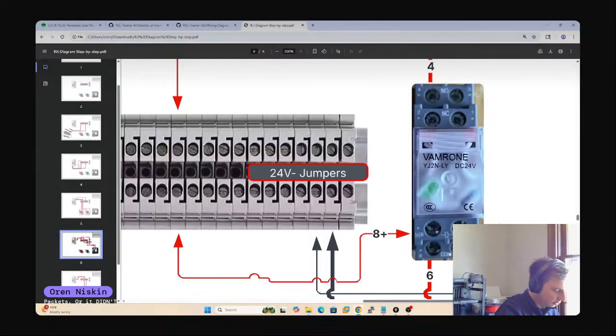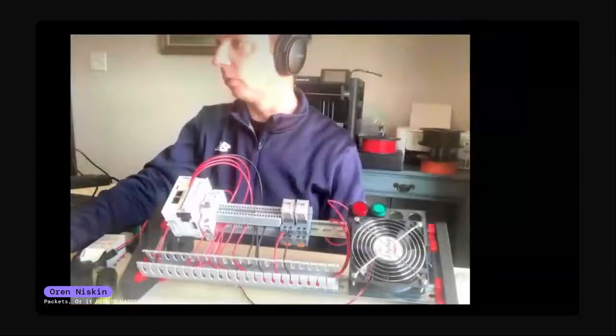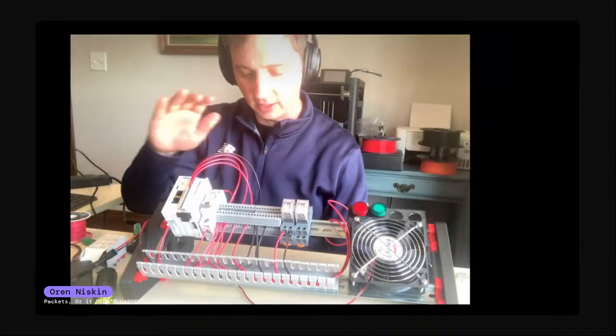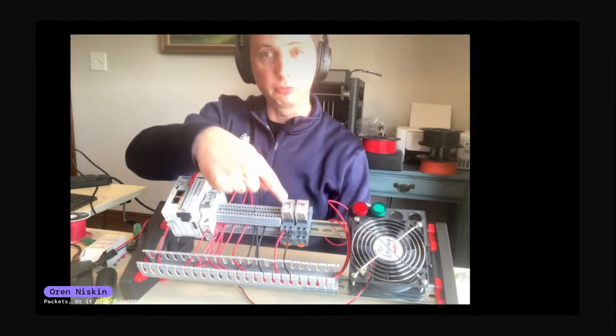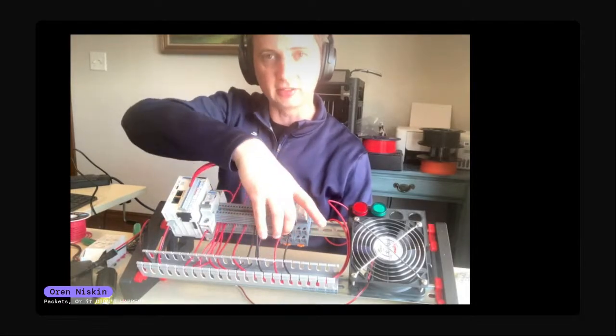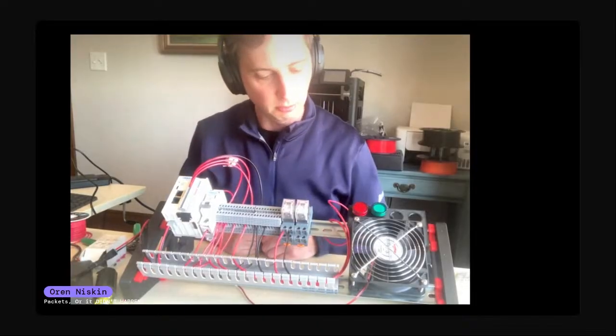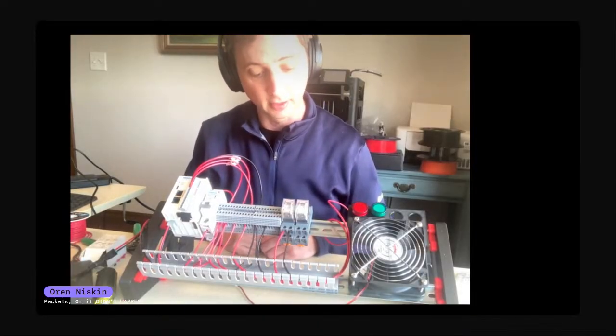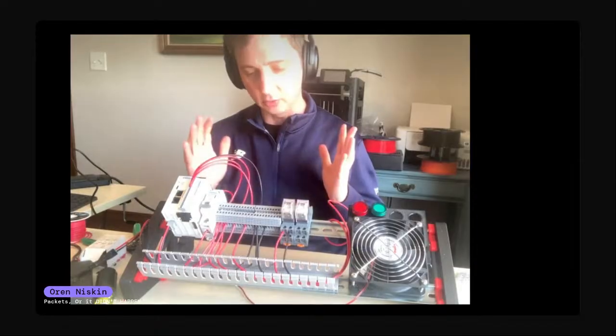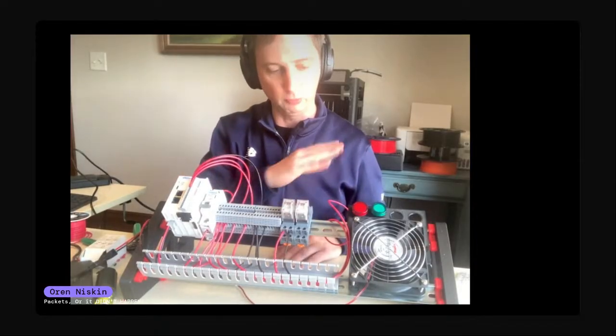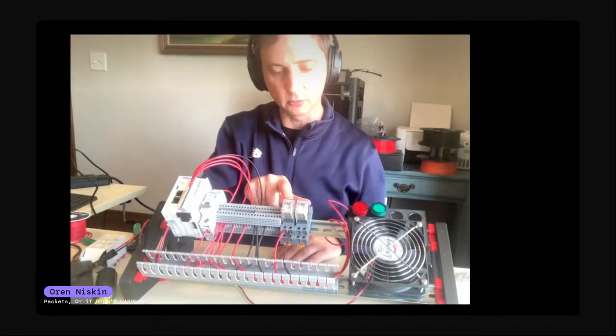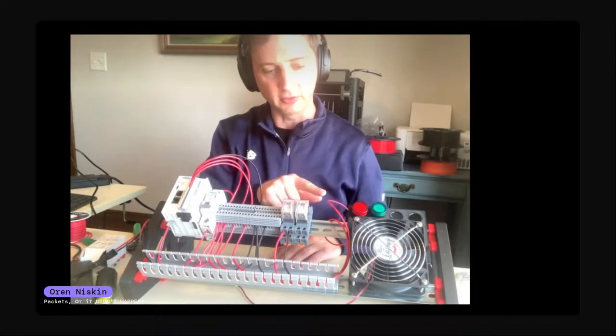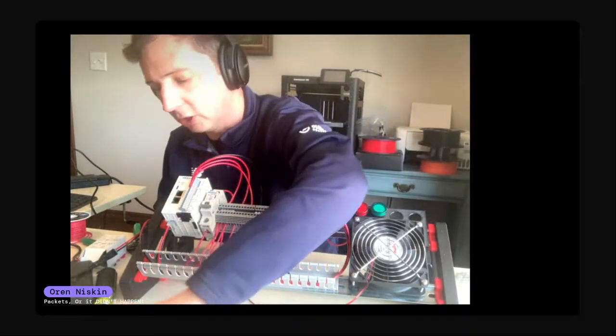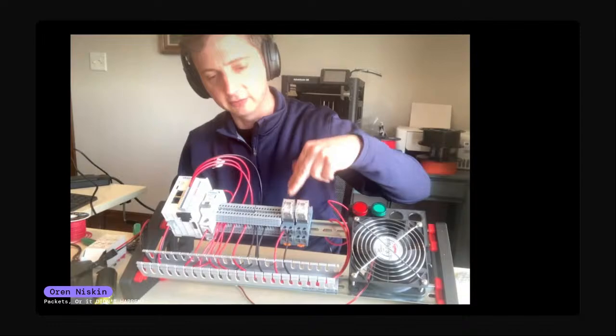Okay, so we have the fan running. We are going to now tie the contacts. So we did the relay, I mean the coil. We're going to do the relay contacts now, and we're going to use normally open because normally open means that when you're not sending the power to it, the fan won't run. When you energize the output, it energizes the relay and starts the fan. You don't want it the opposite. So that is why we're using normally open. When the relay is de-energized, the switch is off.